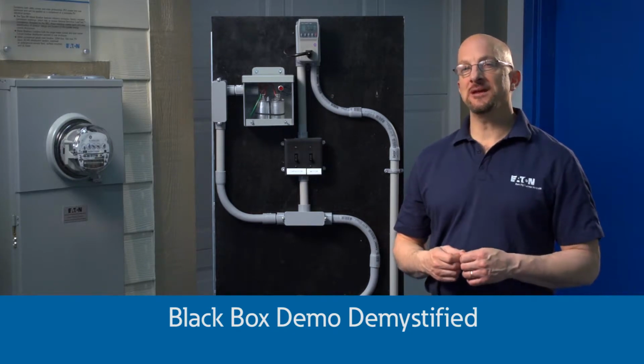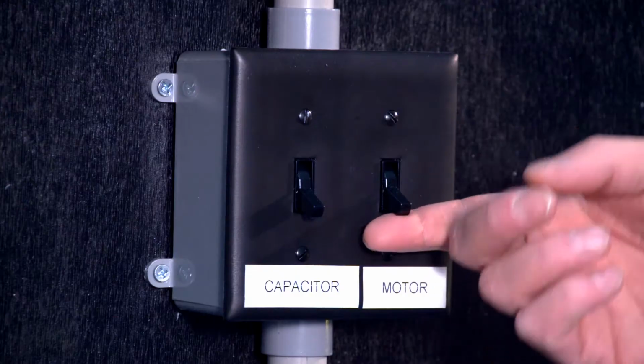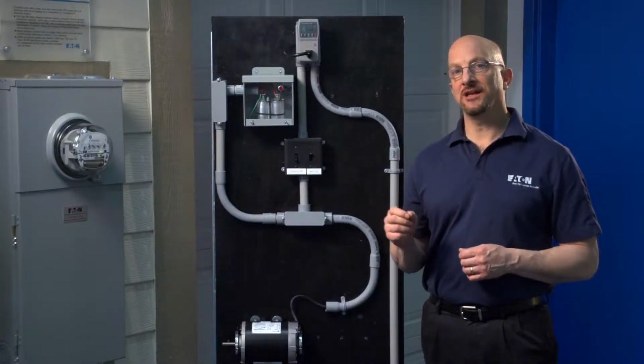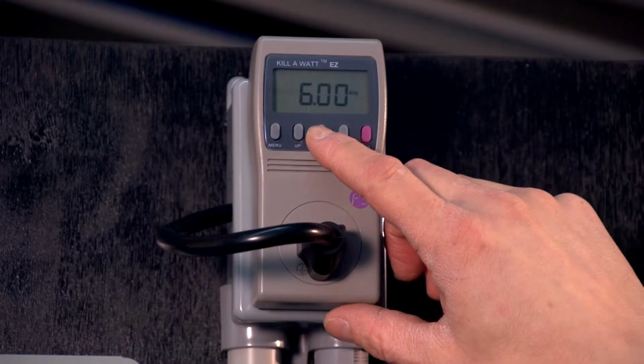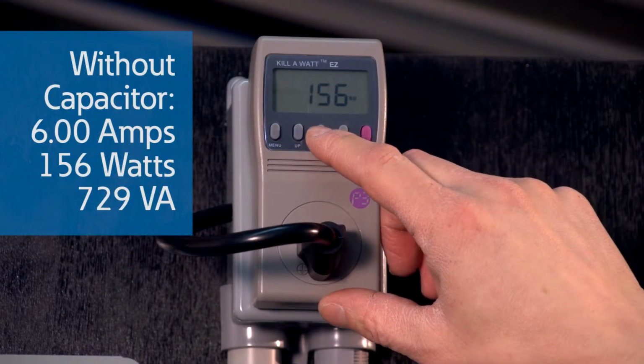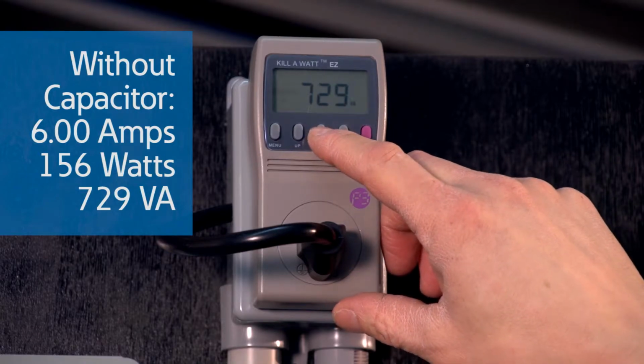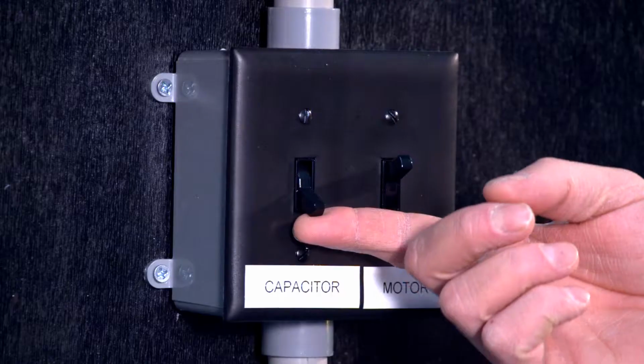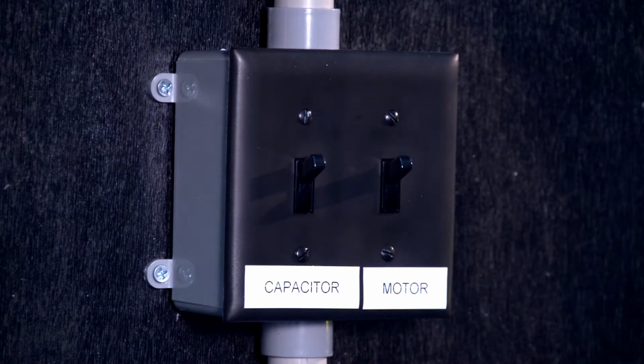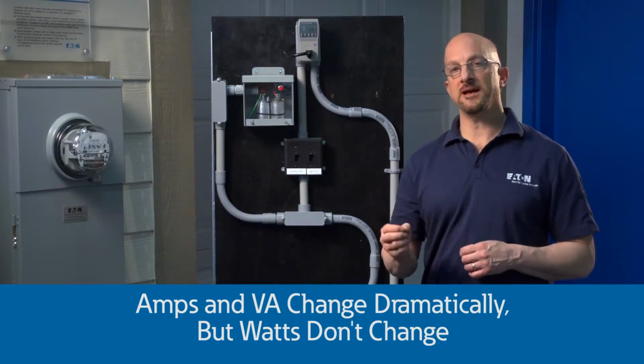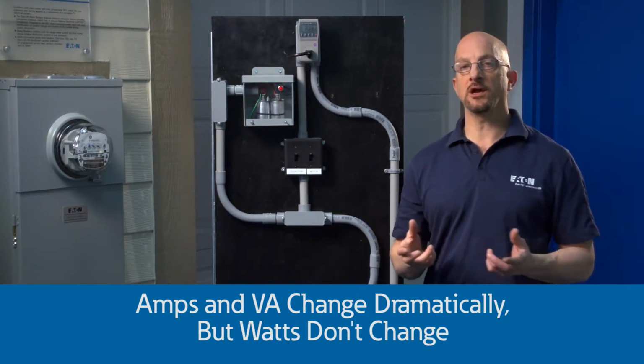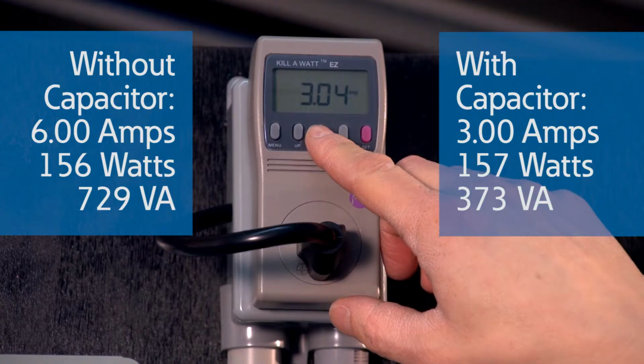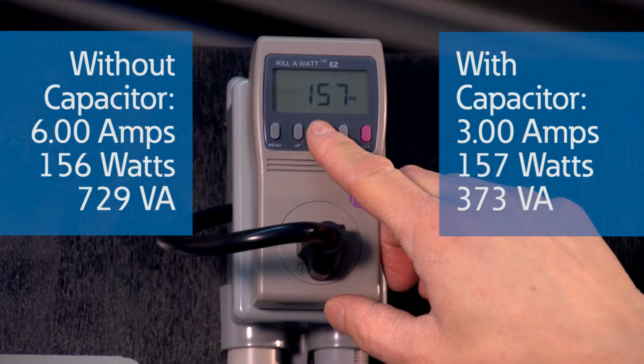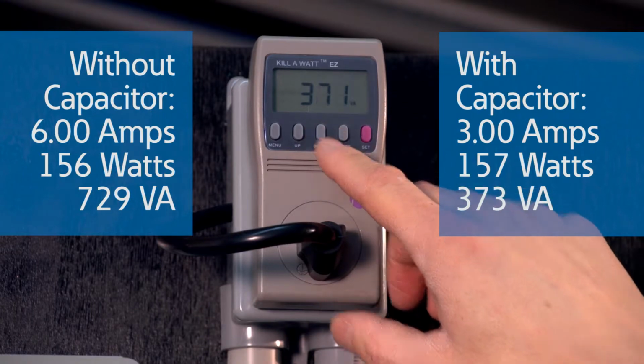Now let's look at that same demo with more detail in the explanation. Interestingly, this simple meter that's been used to prove the savings by showing the amp reduction can also measure watts. The watts don't change when the capacitor is turned on. The amps and the volt-amps, or volts times amps, change dramatically. They're cut in half. The capacitor does nothing, therefore, to the watts, but really only changes the amps and VA.